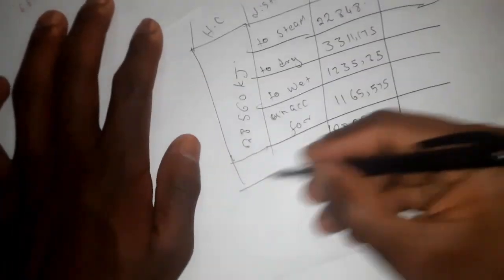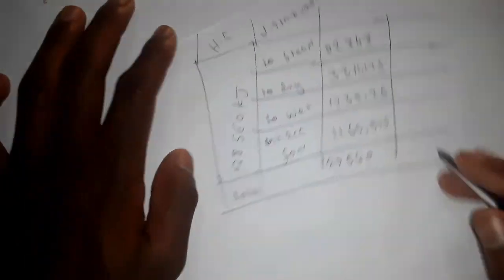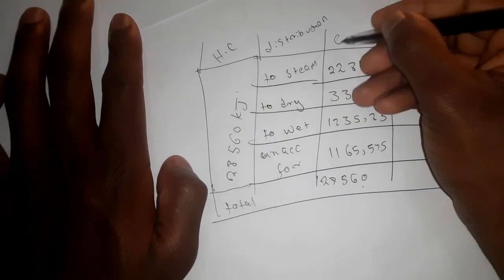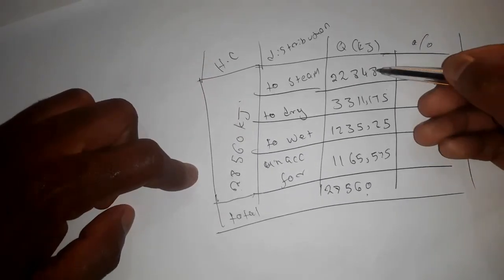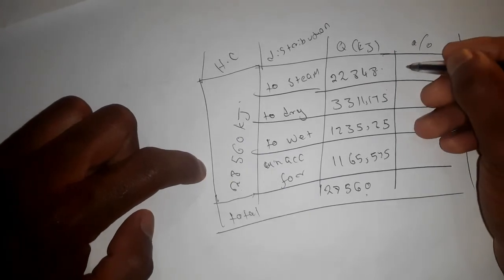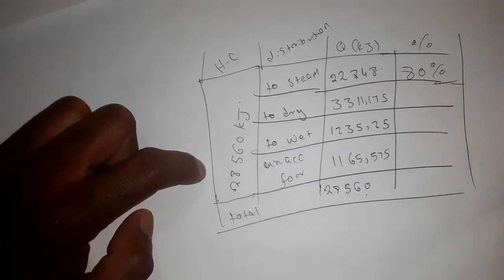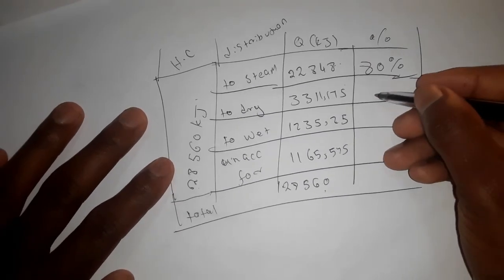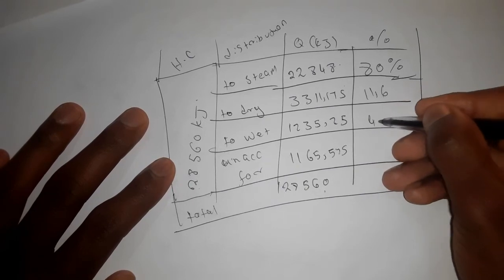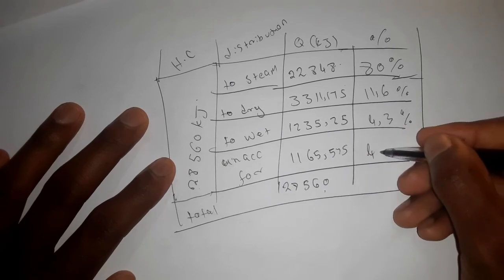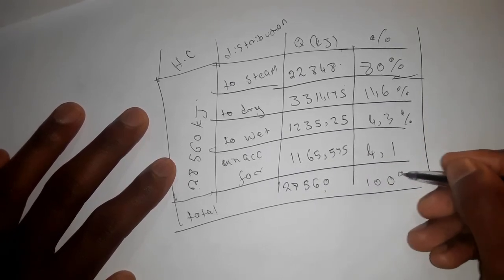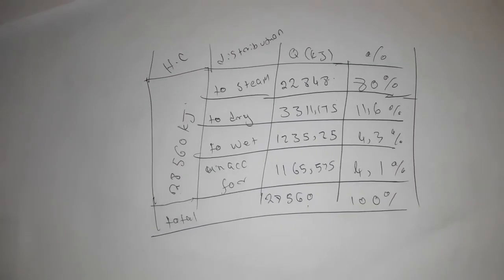Converting each value to a percentage by dividing by 28,560 times 100: heat to steam is 80%, confirming the thermal efficiency; dry gases is 11.6%; moisture is 4.3%; and heat unaccounted for is 4.1%. These sum to 100%. That is all they asked. I will see you on the next lesson. Thank you.